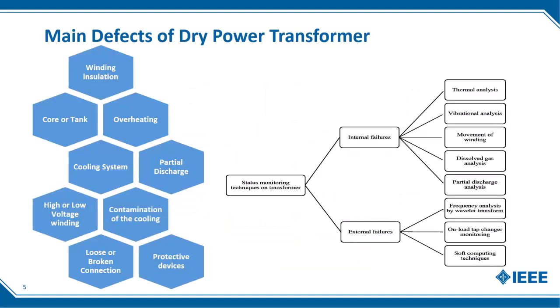Let's focus on the main defects that can occur in dry power transformers. These defects are critical to monitor as they can lead to transformer failures. Dry power transformers are susceptible to thermal overheating and partial discharges.